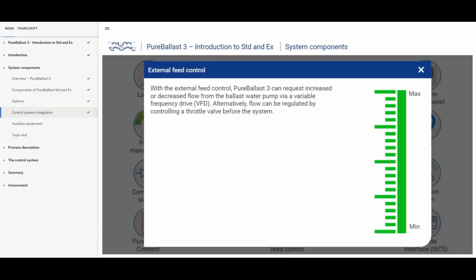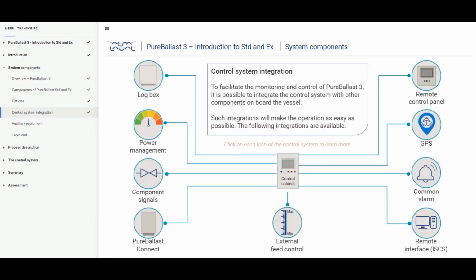With the external feed control, Pure Ballast 3 can request increased or decreased flow from the ballast water pump via a variable frequency drive, VFD. Alternatively, flow can be regulated by controlling a throttle valve before the system. External feed control enables smooth operation, especially during start and stop, reducing the stress on the control valve. Click Next to continue.